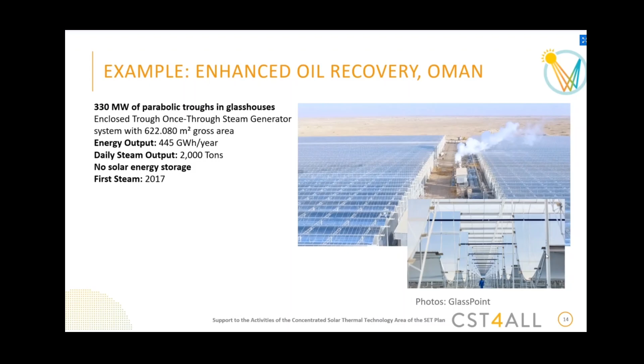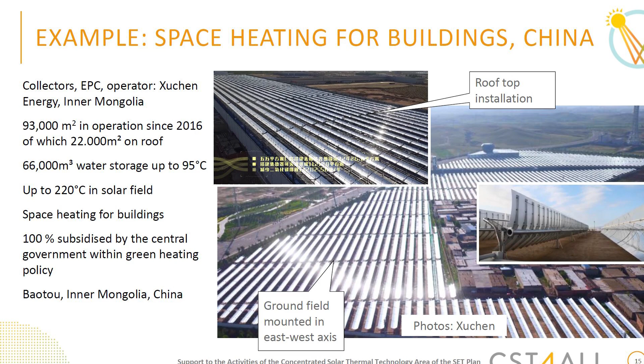In China, they are also building a large system for space heating in buildings - this example is in Inner Mongolia, a 100% subsidized plant by the Chinese government. You see 93,000 square meters of parabolic trough collectors and a huge water storage container of 66,000 cubic meters at 95 degrees. The field delivers 220 degrees and is used for space heating.